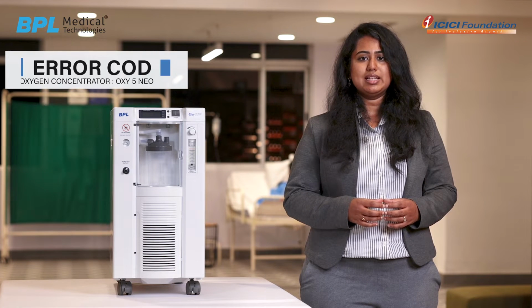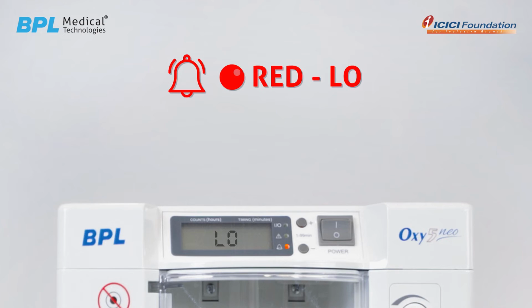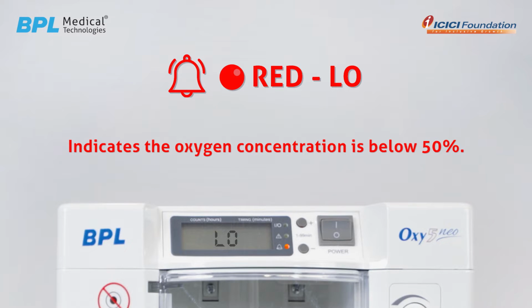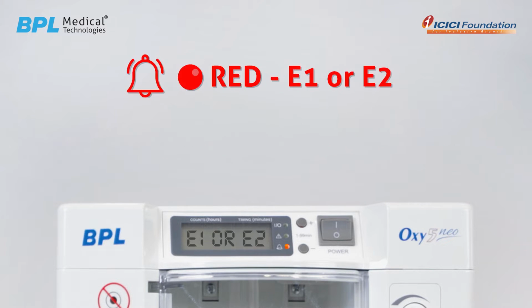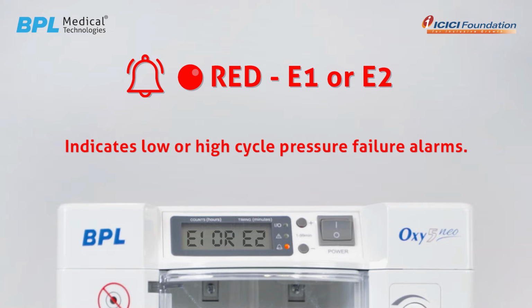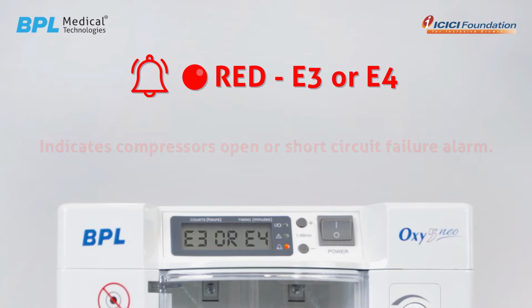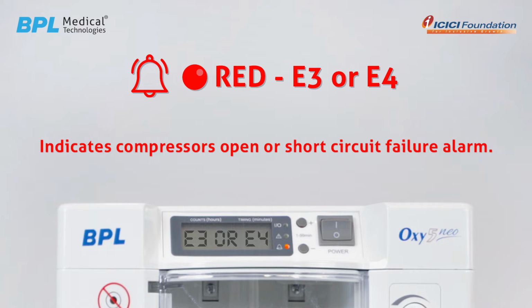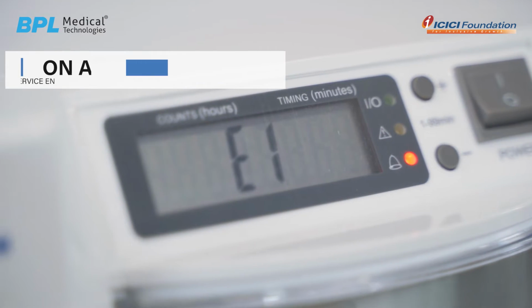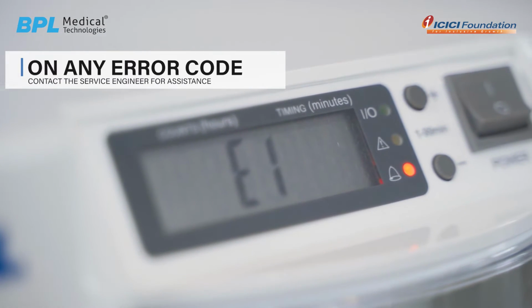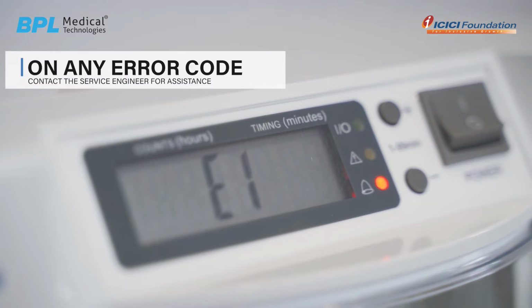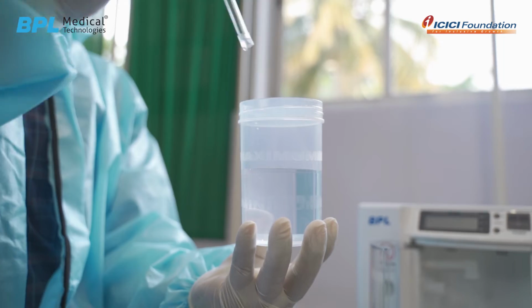Different error codes on LCD screen. Red indicates the oxygen concentration is below 50%. E1 or E2 indicates low or high cycle pressure failure alarms. E3 or E4 indicates compressors open or short circuit failure alarm. If there is any error code of E1, E2, E3, E4, please contact the service engineer for assistance.